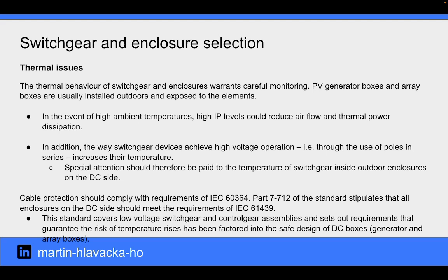The thermal behavior of switchgear and enclosures warrants careful monitoring. PV generator boxes and array boxes are usually installed outdoors and exposed to the elements. In the event of high ambient temperatures, high IP levels could reduce airflow and thermal power dissipation. In addition, the way switchgear devices achieve high voltage operation, for example through the use of poles in series, increases their temperature. Special attention should therefore be paid to the temperature of switchgear inside outdoor enclosures on the DC side.